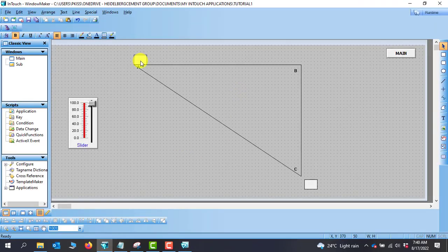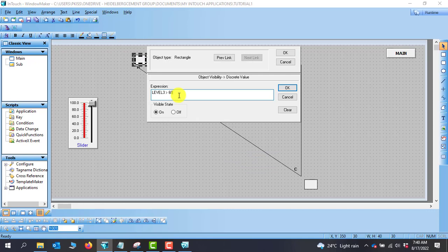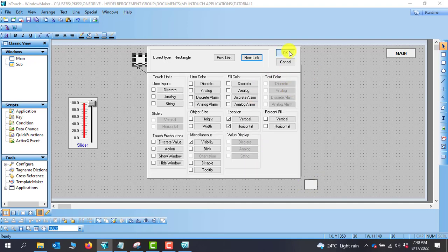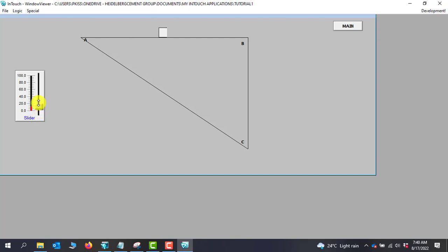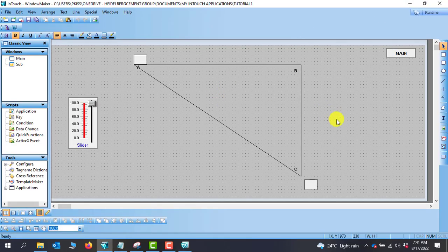This first object must also disappear when the second takes over. We open the first object, go to visibility, and set the condition: when the level is less than 60 this object should be visible, and it should disappear immediately at 60 when the second object takes over. We click OK and go to runtime. Throughout the movement we see only one object, even though we are using two objects in development.